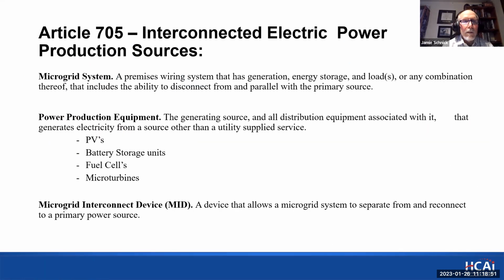Article 705. Now, this is the microgrid solution. And 705 is called interconnected electric power production sources. The microgrid system: a premises wiring that has generation, energy storage, and loads, or any combination, that has the ability to disconnect and parallel with the primary source. Appropriate equipment includes PVs, battery units, fuel cells, microturbines, and the microgrid would have a control device, a microgrid interconnect device that we typically call a microgrid controller.